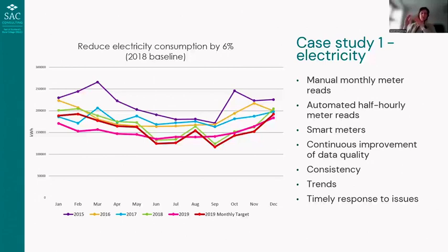They weren't available at the end of August because of holiday and summertime. So it was well into September when they finally took the meter reads. This data was then attributed to August, which caused the spike. And then September, because they were again taking the meter readings at the end of September, became shorter, which showed lower consumption. In reality, this would have been a little bit more spread out, but that's fine.